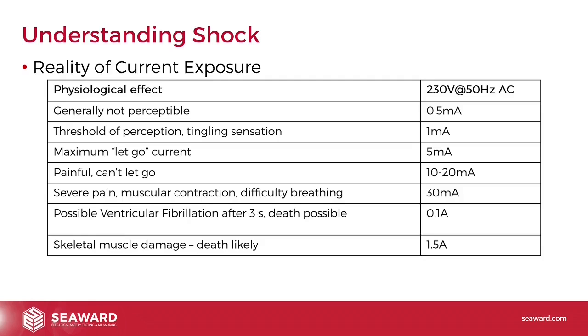I just want to point out a couple of these current levels. So for 5 milliamps, there's probably those of you out there who have recognized this from either production line testing or higher industry testing. This is the limit that's applied by most of the guidance in those areas. I also want to point out the 30 milliamp, that's the common maximum current allowed by the majority of domestic RCD devices. And they're designed to interrupt the supply within a few hundredths of a second to reduce the exposure time if the worst was to happen. So if someone was to get a shock, they're designed to cut that current almost immediately.